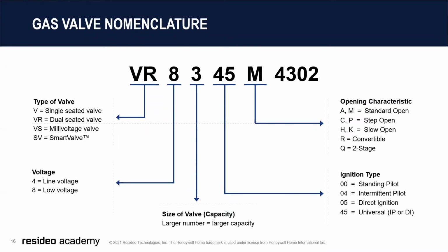The next digit tells you the voltage of the valve, 4 for line voltage and 8 for low voltage. The next digit is the size of the valve, the capacity. Typically speaking, the shortest answer is the larger the number, the larger the capacity for BTUs. The next two digits tell you the ignition type. It's a standing pilot, an intermittent pilot, a direct ignition, or a universal, which means it can be used for both intermittent pilot or direct ignition.